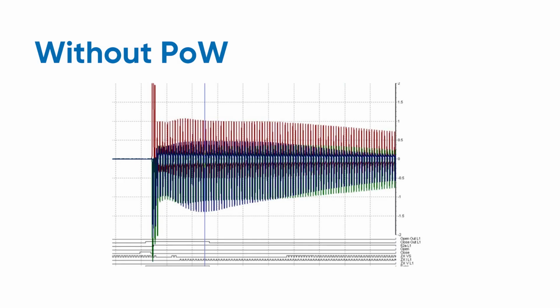So this gives you a little bit of an example of what it looks like without point-on wave. This is the inrush curve, just as we'd shown at the start, from a transformer energized without point-on wave. This is a real-life waveform from the site. When we arrive at site and our commissioning engineers start to program the relay, the first operation we have, there's no timing, there's no flux. So you get a random operation that looks like this.